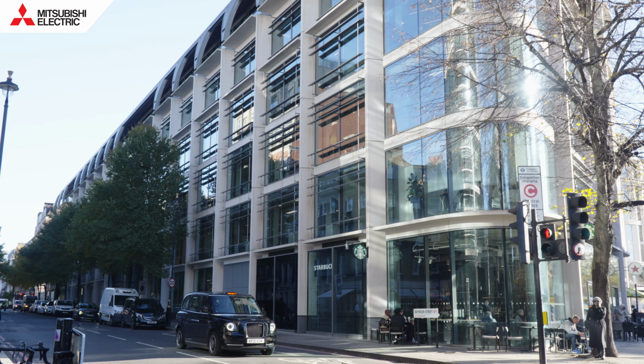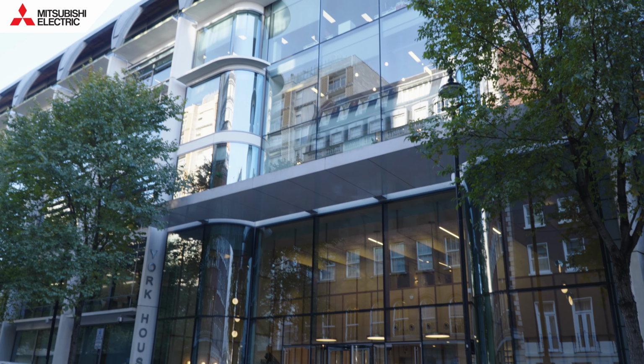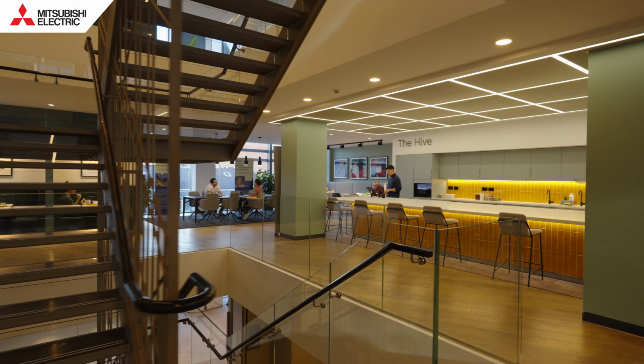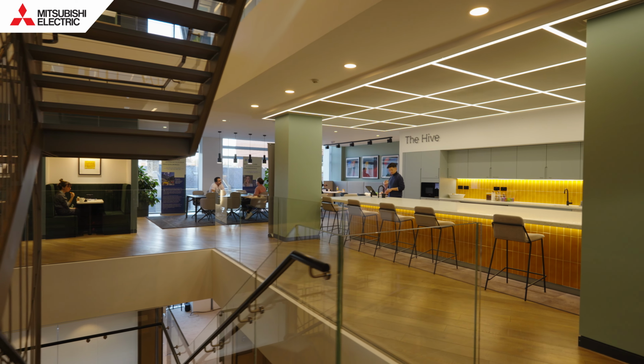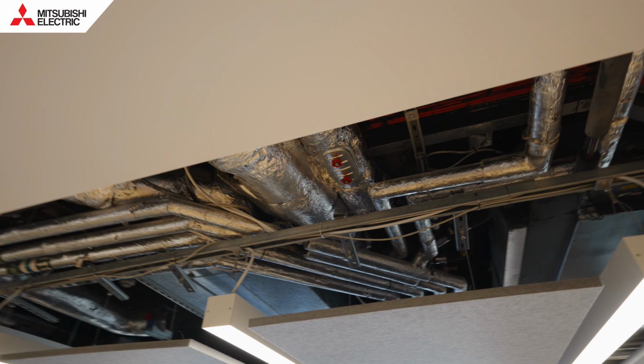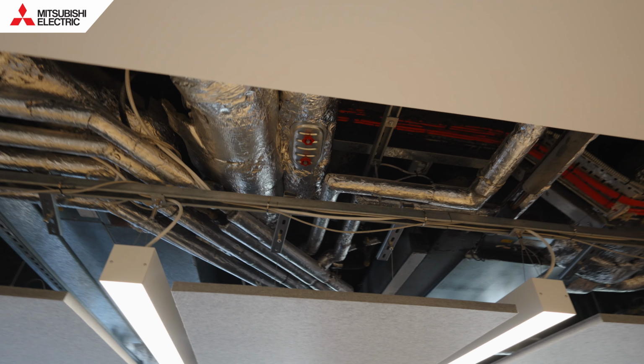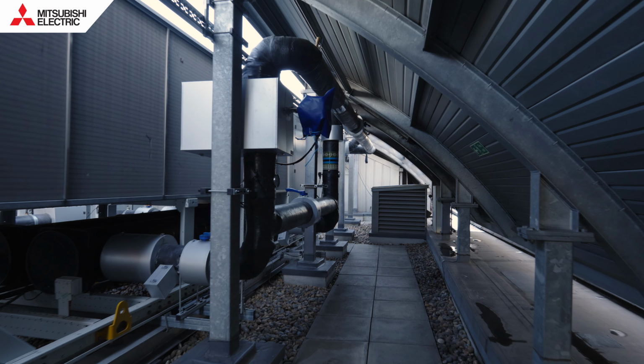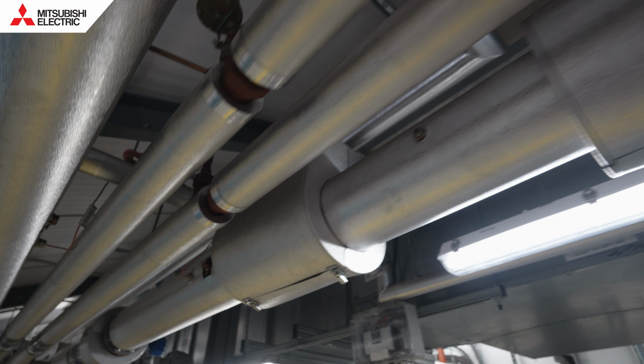York House is a commercial property with 5 floors, with various occupiers across those floors. Recently, the project to remove the carbon from the building was to remove all of the gas from the office side of York House. That involved removing 4 gas boilers and installing 2 air source heat pumps and the associated equipment to keep the heating system going.